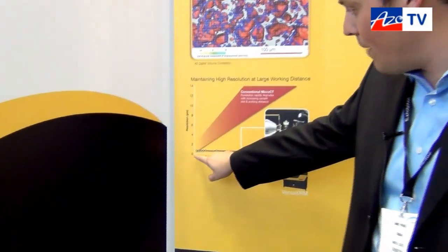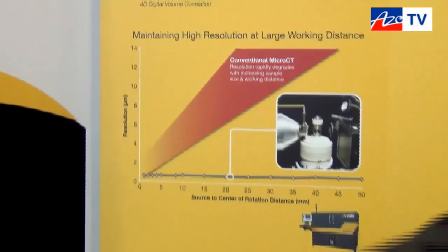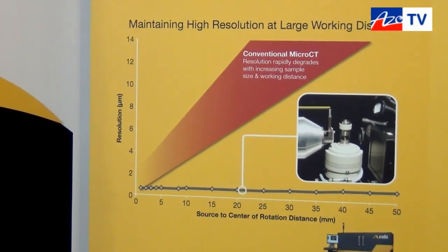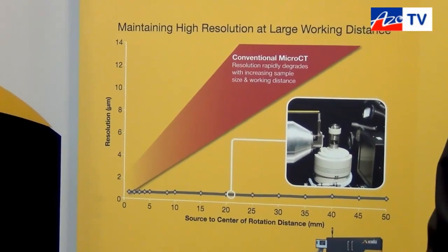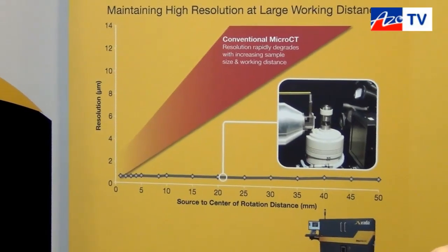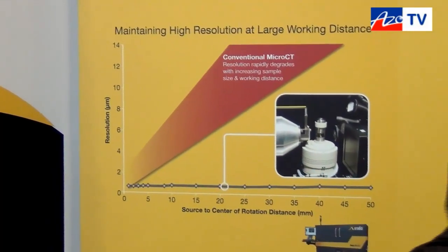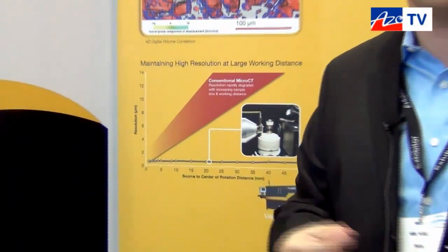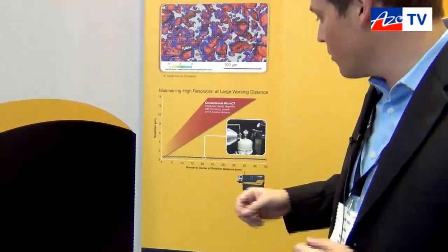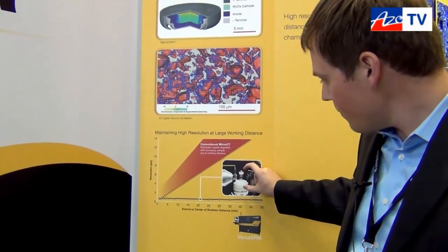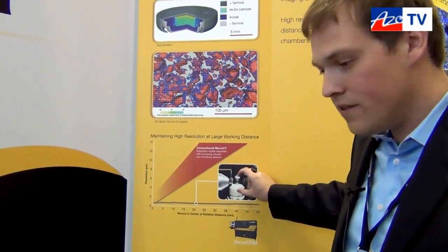We can maintain resolution that's better than 700 nanometers and better than a micron over very large source distances and working distances. We can maintain this over many tens of millimeters, which means you can look at small regions of a larger sample inside, and you can also look at it inside in-situ stages, which are tension, compression, or heating and cooling.